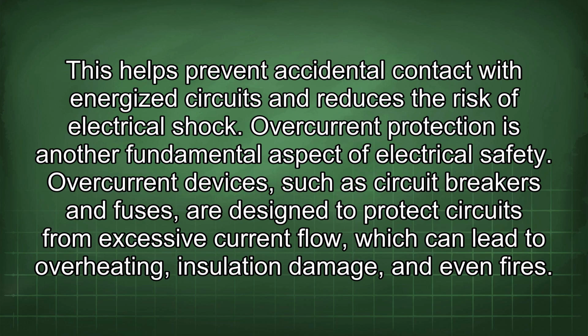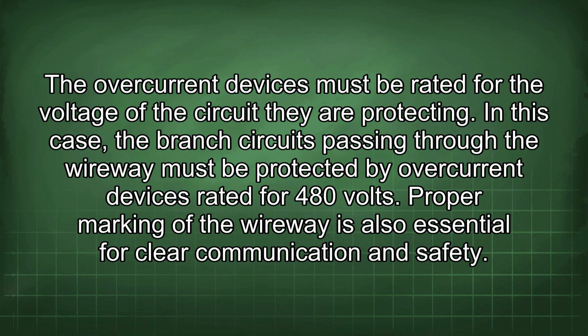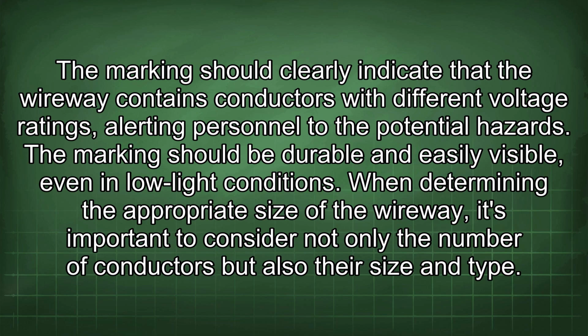Overcurrent protection is another fundamental aspect of electrical safety. Overcurrent devices, such as circuit breakers and fuses, are designed to protect circuits from excessive current flow, which can lead to overheating, insulation damage, and even fires. The overcurrent devices must be rated for the voltage of the circuit they are protecting. In this case, the branch circuits passing through the wireway must be protected by overcurrent devices rated for 480 volts. Proper marking of the wireway is also essential for clear communication and safety. The marking should clearly indicate that the wireway contains conductors with different voltage ratings, alerting personnel to the potential hazards. The markings should be durable and easily visible, even in low light conditions.